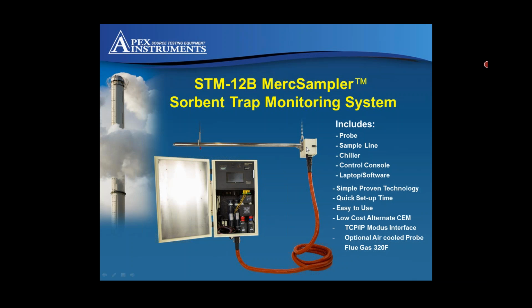So the sample is going to come down the probe to our heated junction box, where we make a union with our umbilical cord here. Our heated umbilical cord will bring the sample down, around, and join into the console box here, into the system. Then, keeping it real basic, we're going to take the sample into our Stirling chiller here. We're going to make our moisture knockout, so we chill that sample down and remove the moisture, which is going to collect in these bottles.